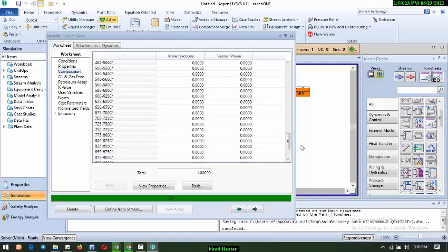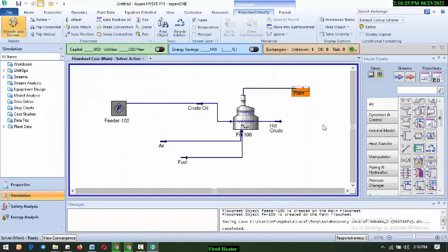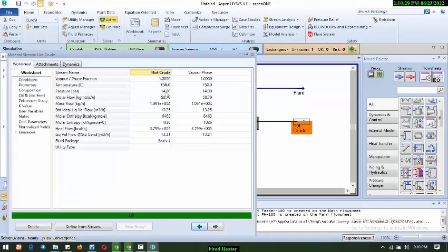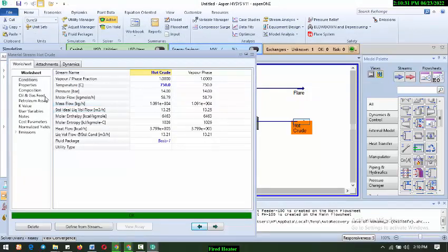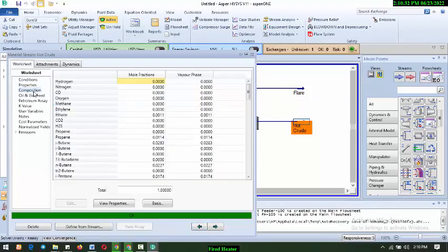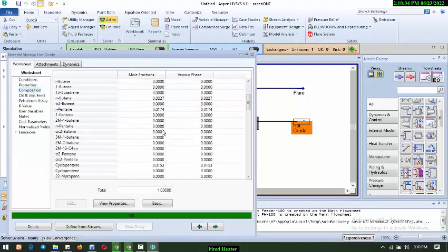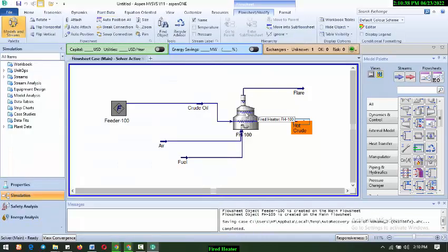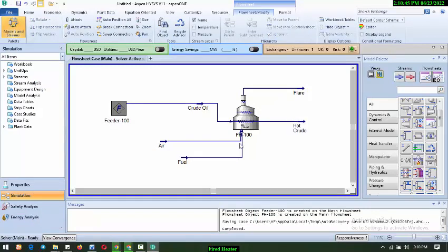You can also check your hot crude. So you have your 750, and everything is solved. So this is your crude oil, probably you want to heat up to 750 before you send it to another unit, probably for distillation, whatever you want to, fractionation, whatever you want to do, you will include at the end of the day. So this is how to model your fire heater.